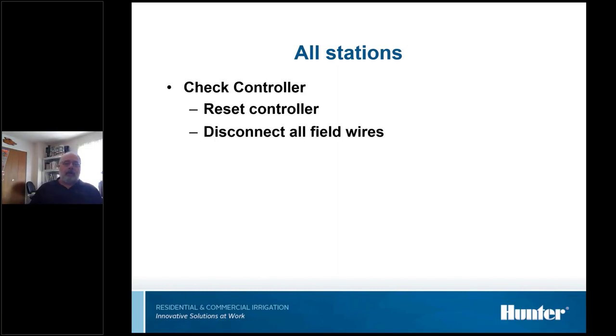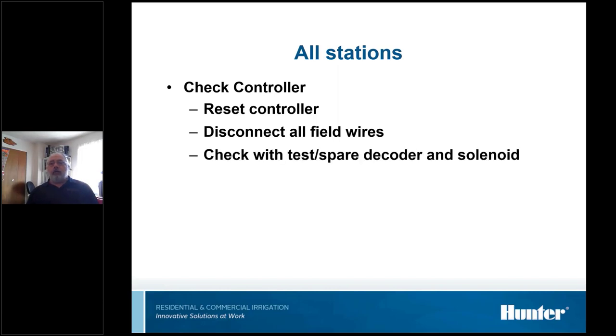From there, as long as that's not what it is, the steps we take is we're going to disconnect all the wires in the controller, no matter how many wire paths it has, we're going to take them all off, and we're going to prove the controller works. And we use the spare decoder and solenoid. I literally hook them to each other, and then hook that to the terminal strip of the controller and see if I can turn that decoder on.